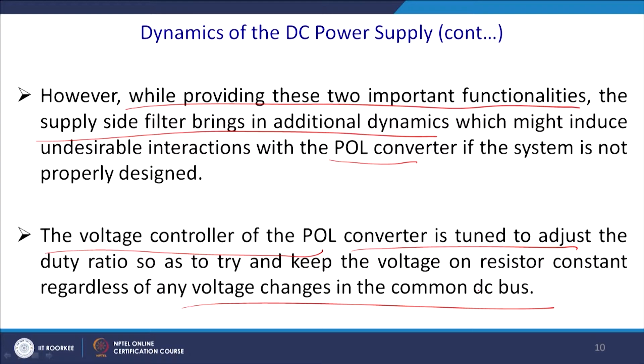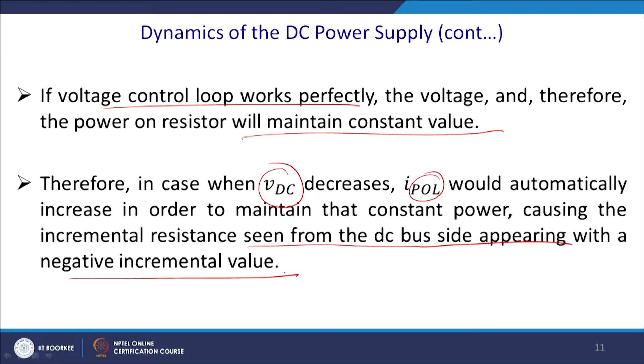And what happens then: if the voltage control loop works perfectly, the voltage and therefore the power on the resistance remains a constant value, then there is no problem at all. Therefore, in case of VDC decrease, the I of this point of load will automatically increase in order to maintain the constant power, because the incremental resistance seen from the DC bus side appears with a negative incremental value. So if voltage decreases, current has to increase, and thus you have a negative resistance characteristic. Positive resistance is healthy, but a negative resistance is quite detrimental, and you have to control it.